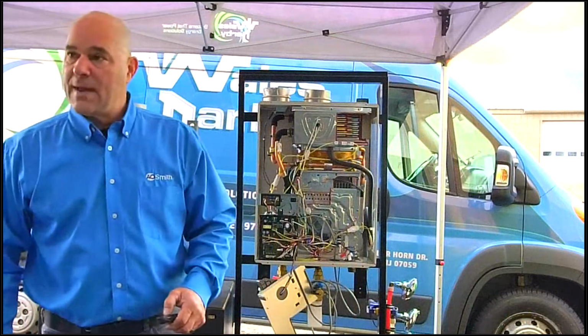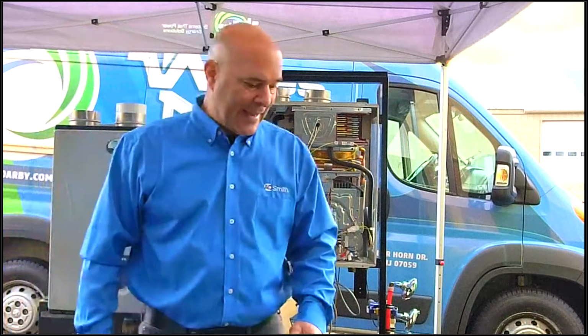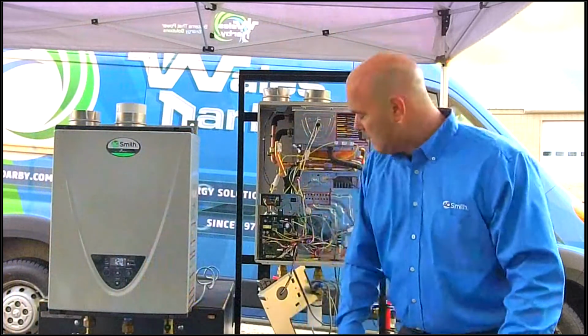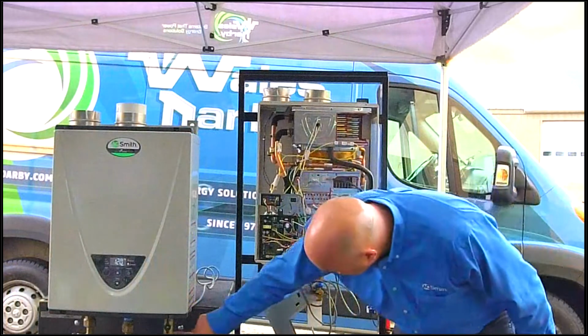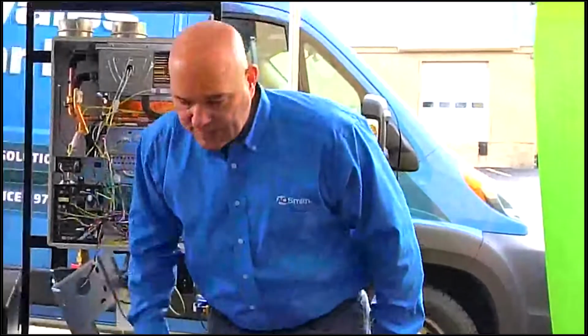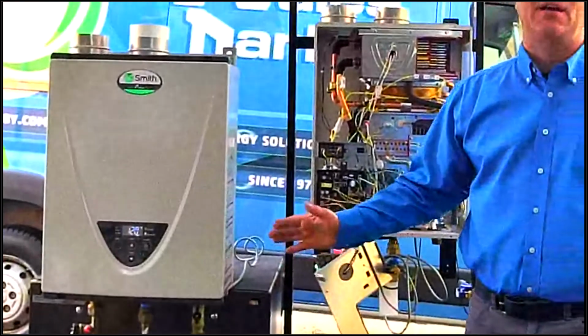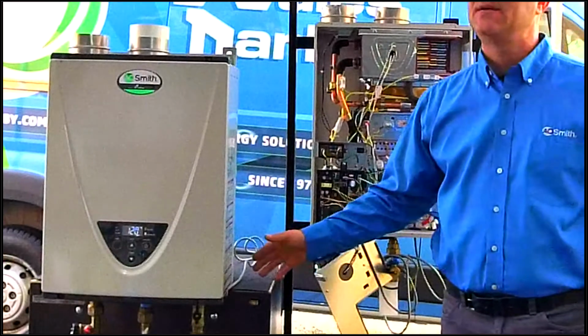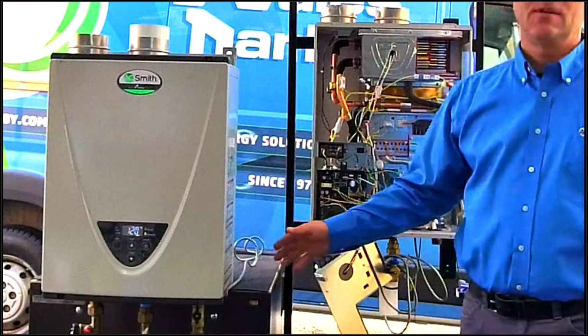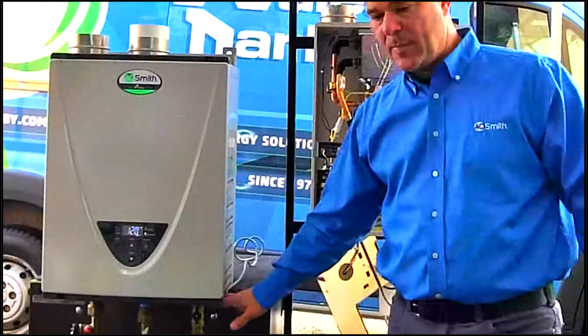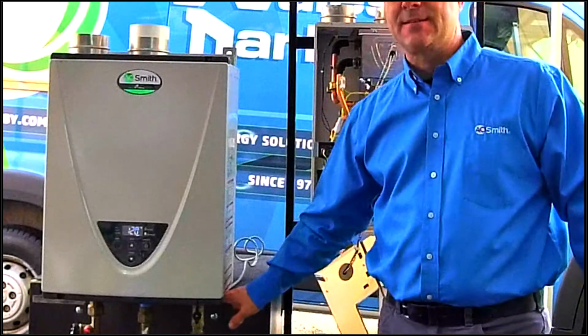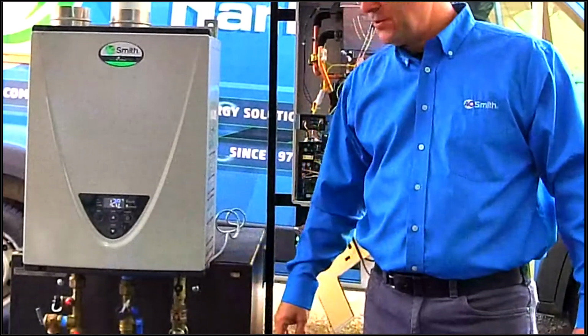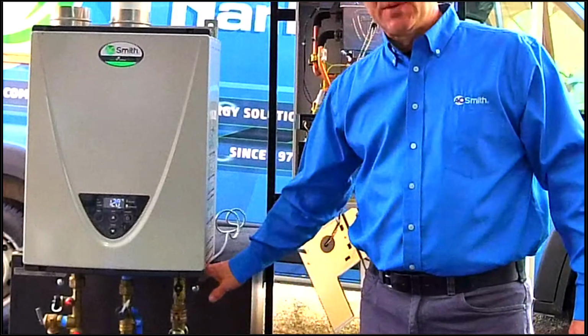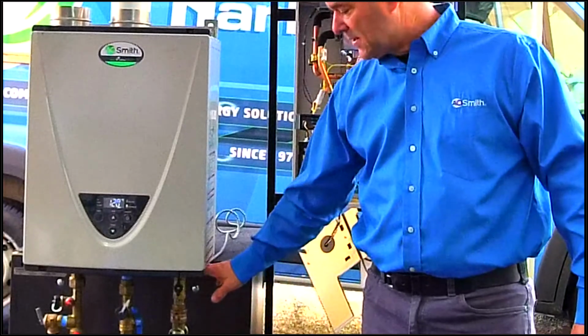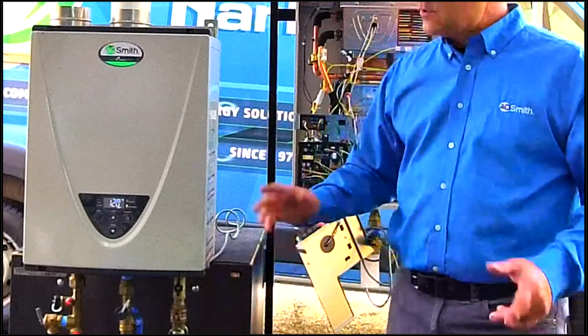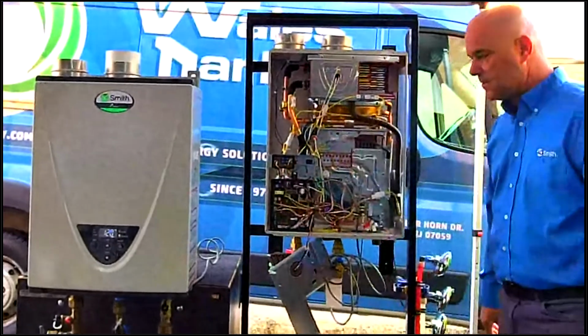So we're going to talk about the gas side of things. We have a gas inlet right here. It's critically important that you back that up when you put your gas valve on. It is critically important because we have had a couple guys twist this and had gas leaks at the unit. So make sure we twist that. Make sure we get it in place. Everything is good. Use your thread compounds and so on.